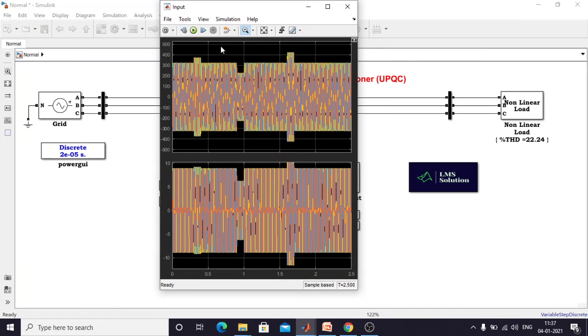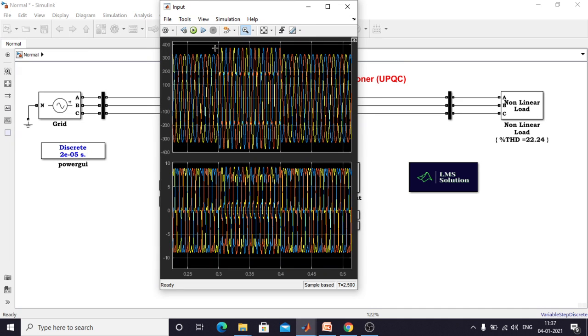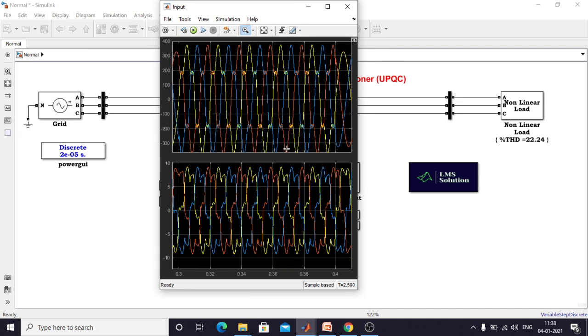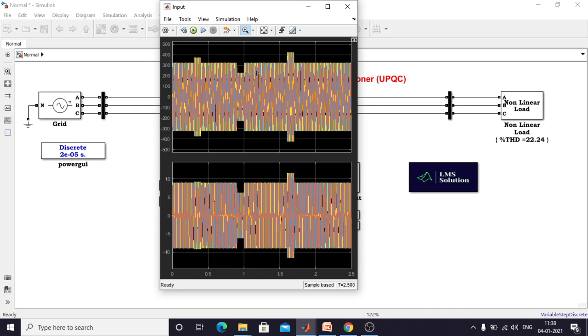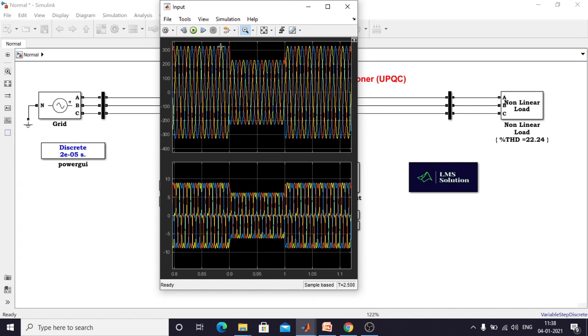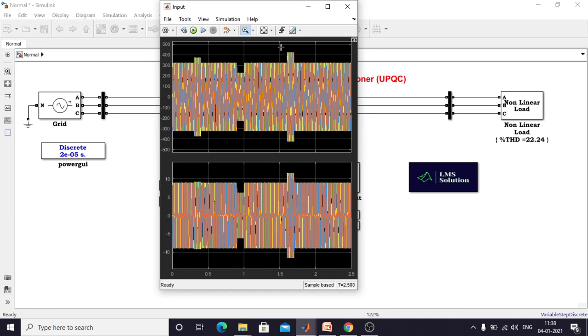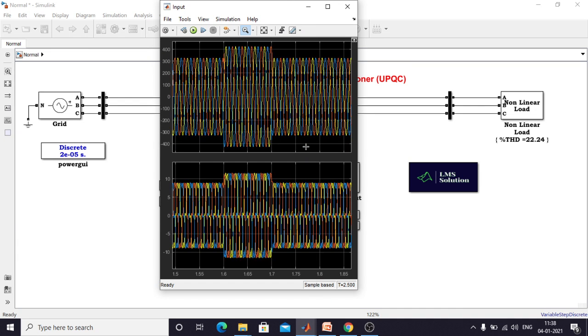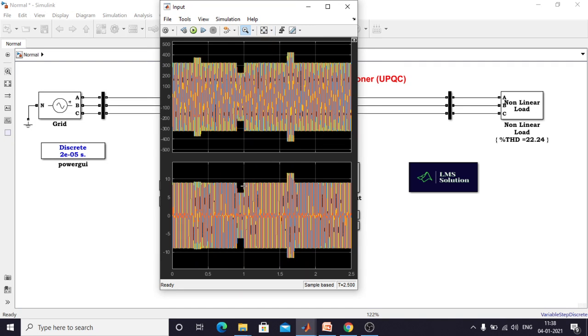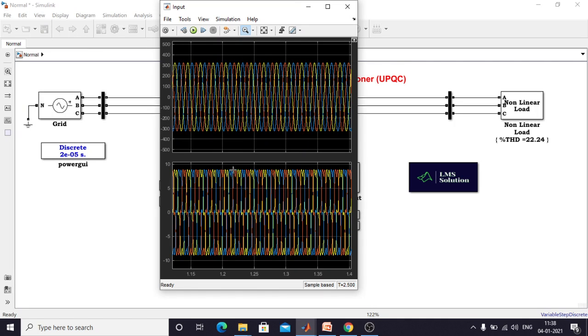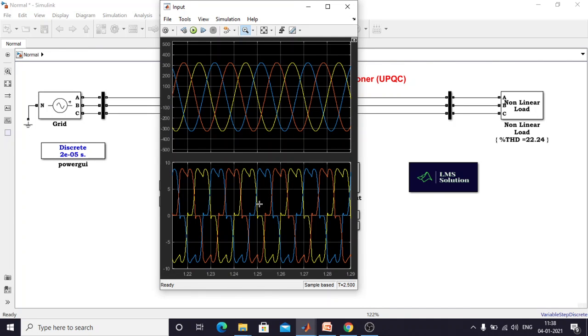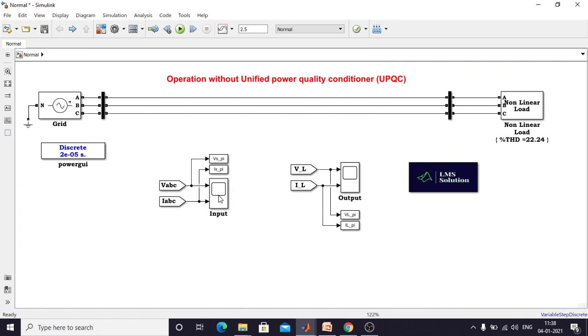This is source voltage and current. Here you can see the generation of harmonics in the source voltage. This is the generation of voltage sag — the amplitude changes from 1 per unit to 0.7 per unit. This is the generation of voltage swell — the amplitude changes from 1 per unit to 1.3 per unit. This is the input source current variation. The current is not sinusoidal — it has some distortion.